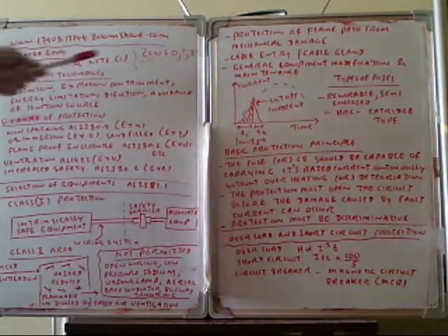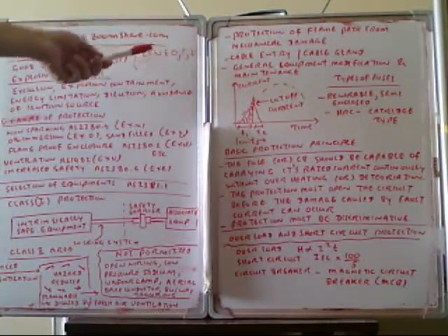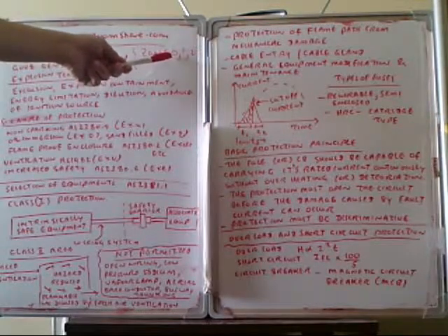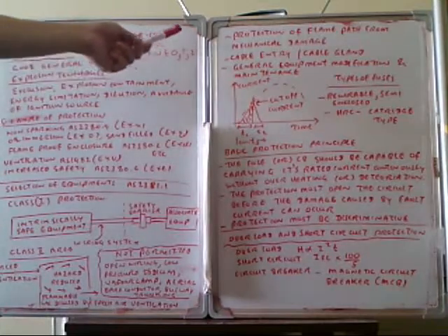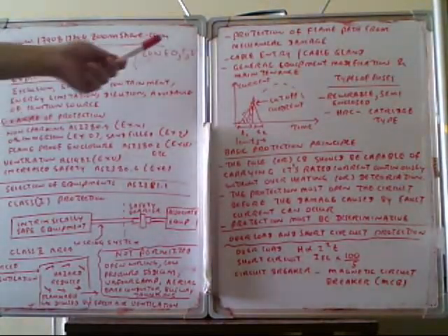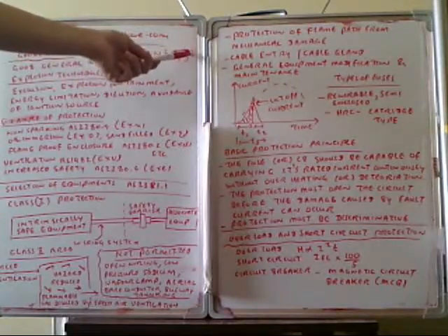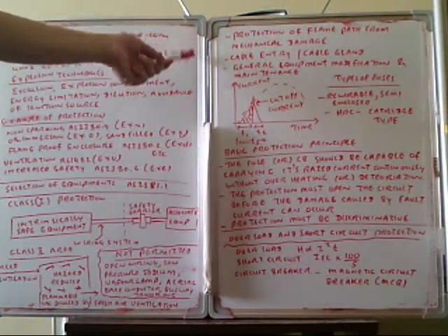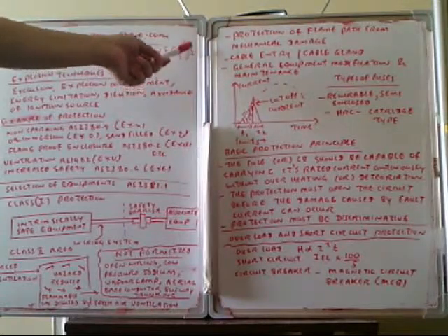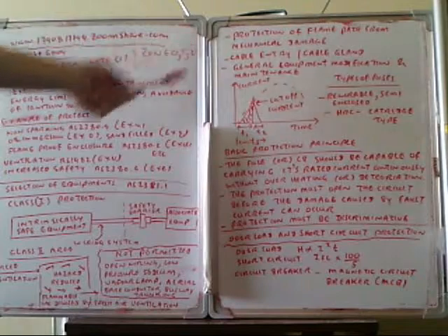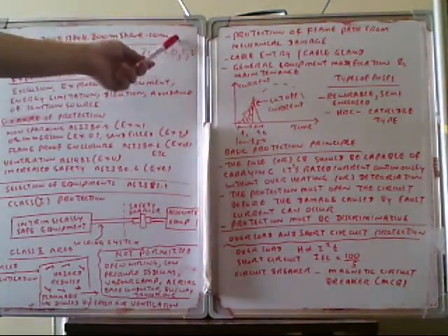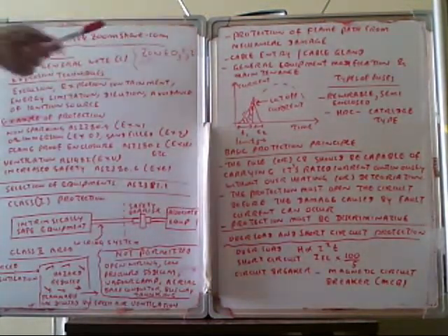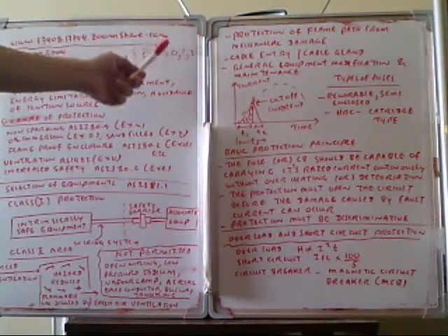In the industry, the hazardous zone can be classified as zone 0, zone 1, and zone 2. Zone 0 is where hazardous gas, for example petroleum gas, is continuously present all the time. Zone 1 is where it can sometimes be present, for a certain period. Zone 2 is where the possibility of hazardous gases happening is low, and even if they are present, the duration is short. So zone 0 is continuous, zone 1 is for some time, zone 2 is a very short time. Depending on whether hazardous gases are present in the area, the zone can be classified as zone 0, zone 1, or zone 2.